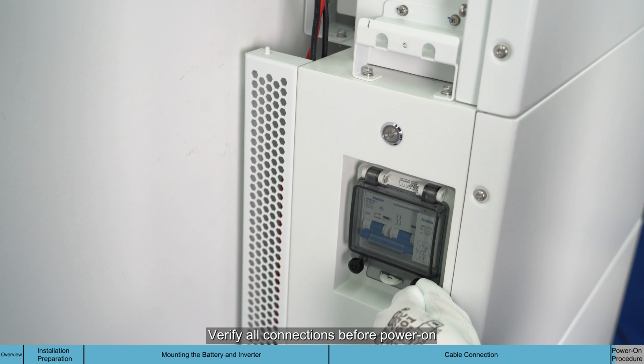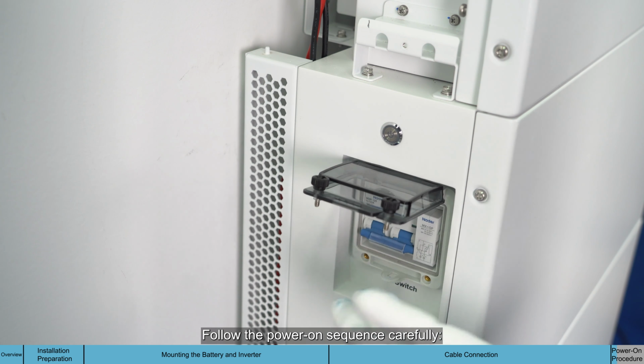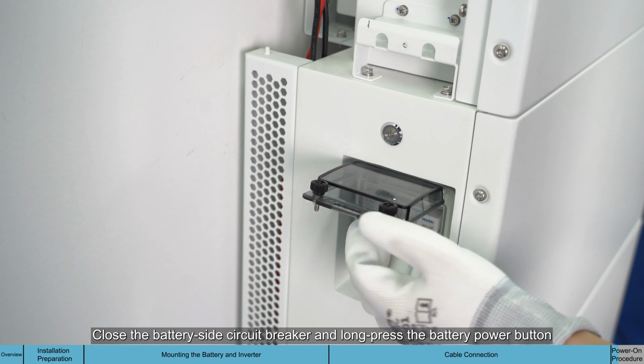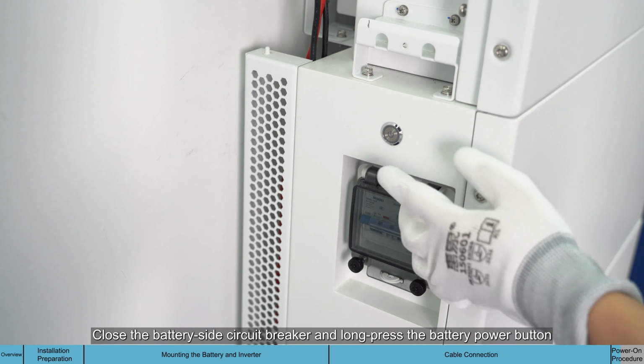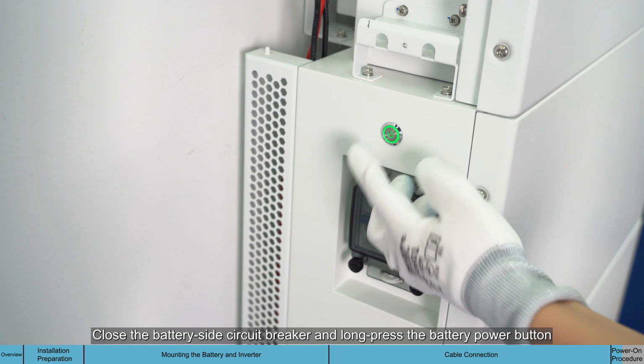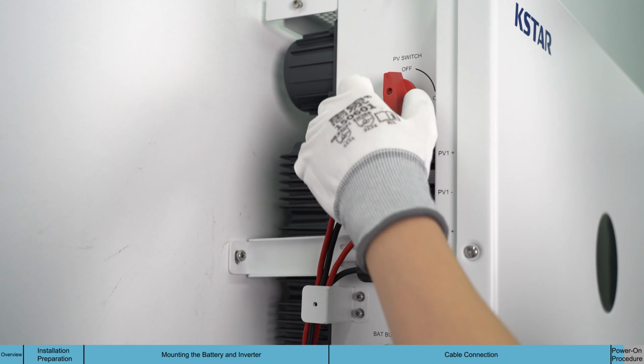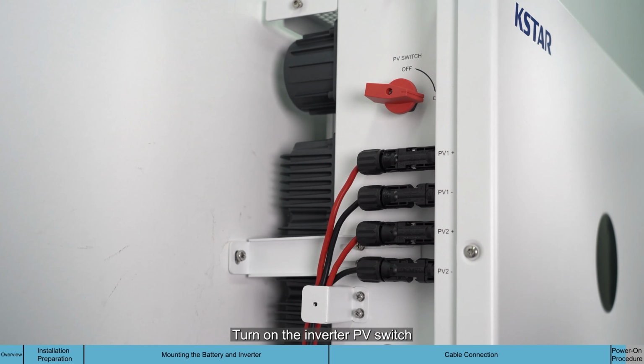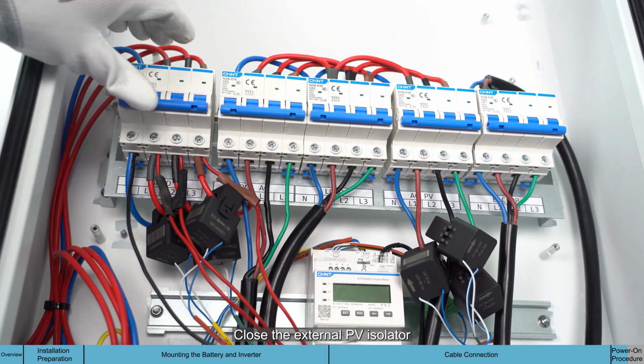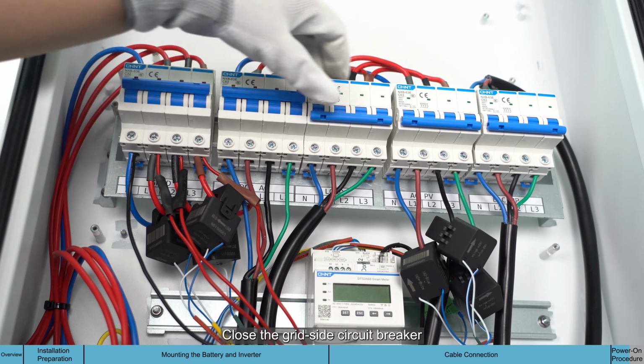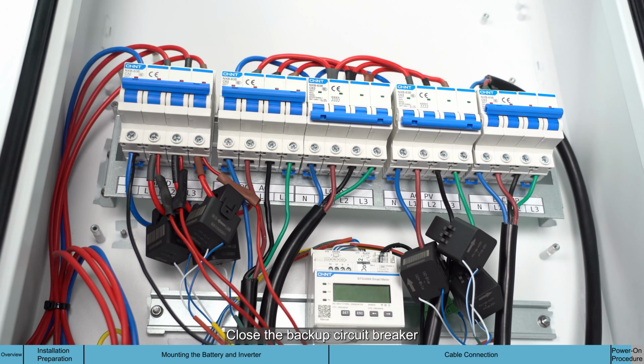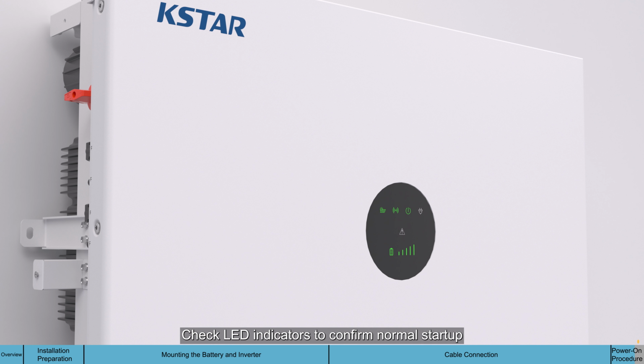Verify all connections before power on. Follow the power on sequence carefully. Close the battery side circuit breaker and long press the battery power button. Turn on the inverter PV switch. Close the external PV isolator. Close the grid side circuit breaker. Close the backup circuit breaker. Check LED indicators to confirm normal startup.